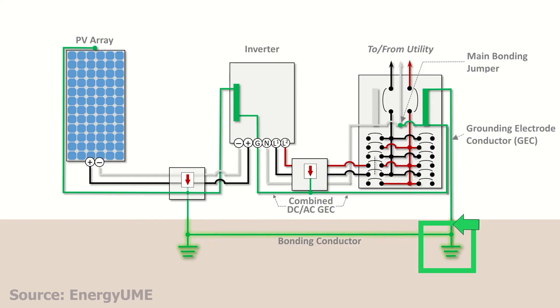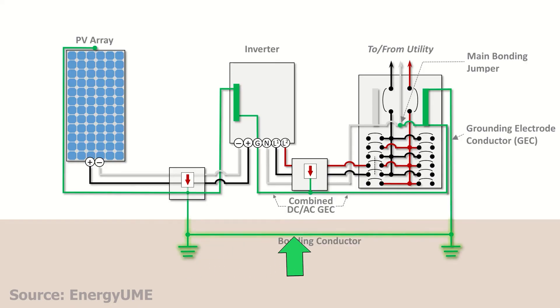The grounding system ties into your main service grounding electrode — usually a ground rod or a Ufer connection. The ground rod must be at least eight feet long, driven fully into the earth. It can be copper or galvanized steel, but if you're using aluminum wire it cannot touch soil or concrete — that's per NEC 250.64(A), which literally forbids it. If you install a separate ground rod for your array, it must be bonded back to your main house grounding system with a continuous copper wire — never leave it isolated, as that can create a dangerous voltage difference between your house and your solar array.